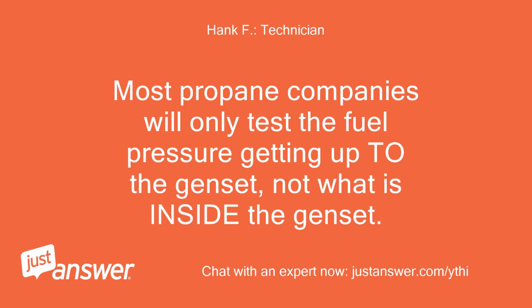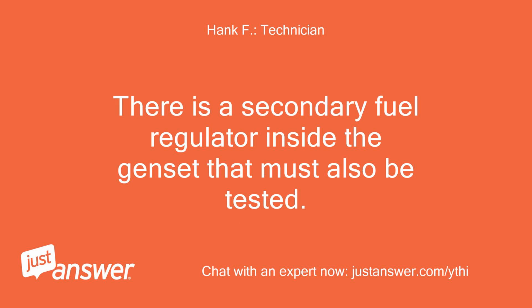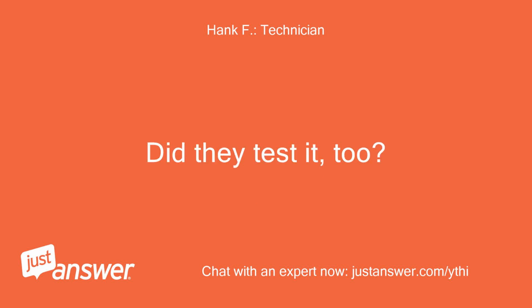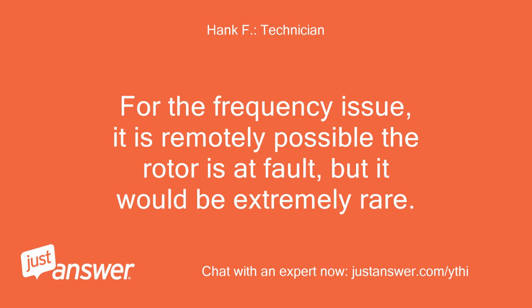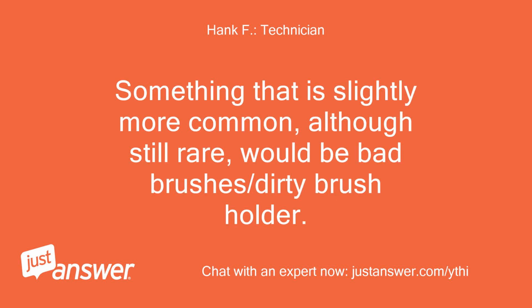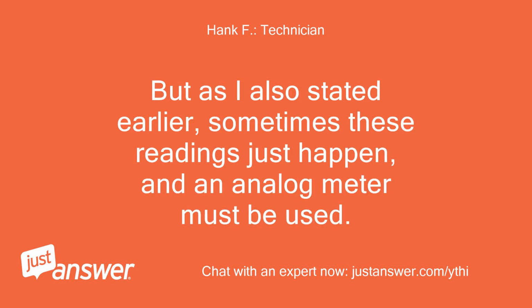Most propane companies will only test the fuel pressure getting up to the genset, not what is inside the genset. There is a secondary fuel regulator inside the genset that must also be tested. Did they test it, too? For the frequency issue, it is remotely possible the rotor is at fault, but it would be extremely rare. Something that is slightly more common, although still rare, would be bad brushes or a dirty brush holder. But as I also stated earlier, sometimes these readings just happen, and an analog meter must be used.